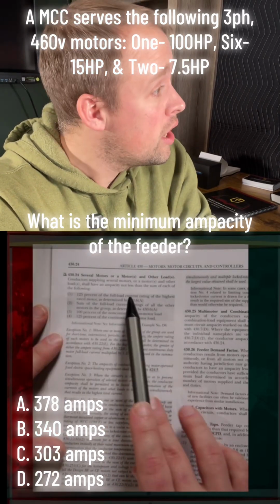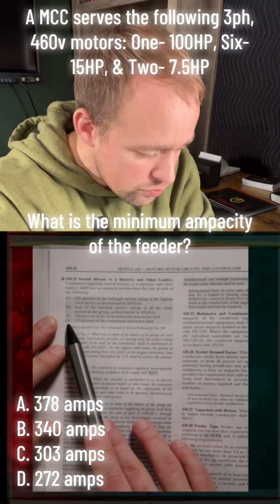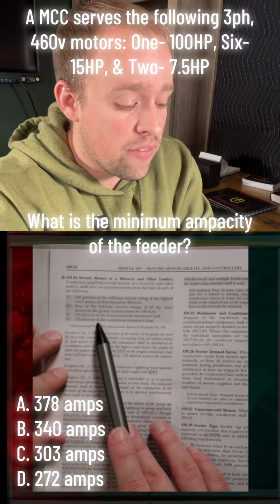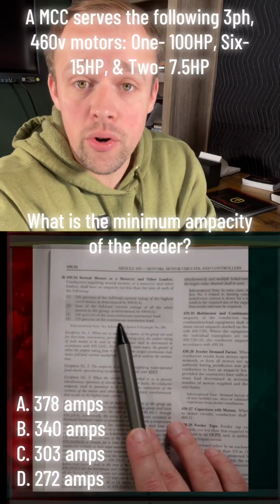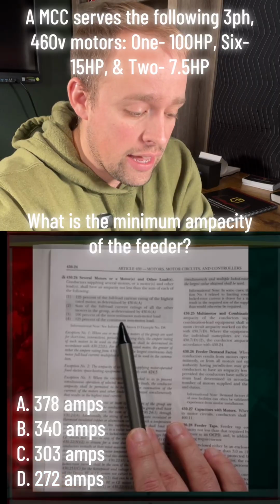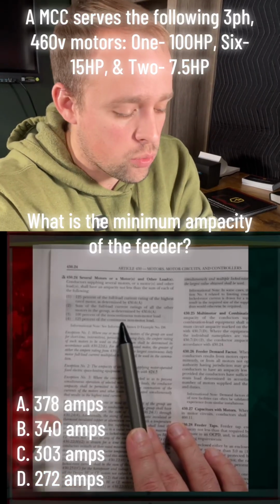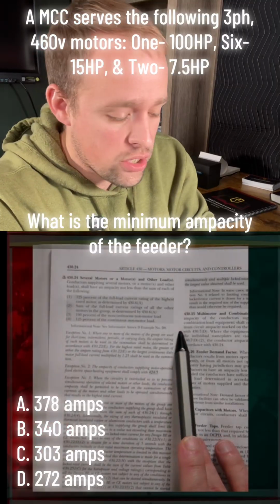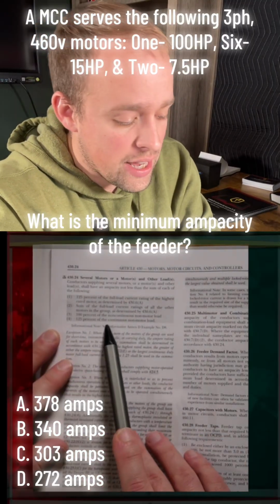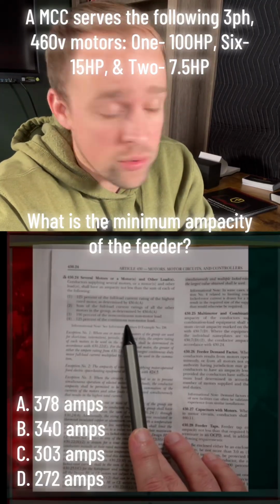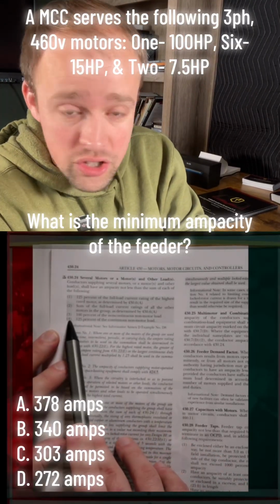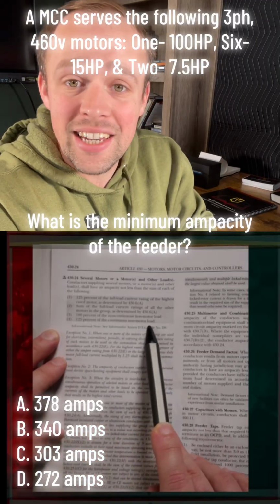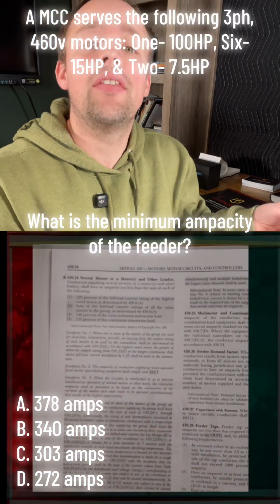So again, it's important to understand 430.24. 3 says 100% of the non-continuous non-motor load. Our question doesn't have a non-continuous non-motor load, so we're going to ignore 3 for this question. 4 says 125% of the continuous non-motor load. Our question doesn't have that. So for this question, we're skipping 3 and 4, but we do need to get an ampacity for 1 and 2 and then add them together.